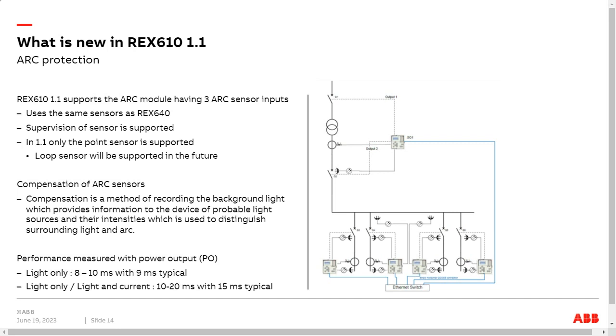Then there's something new here also, something called compensation of ARC sensors. This is something that you should do in the beginning. What it means is that you open up all the doors to the switchgear, switch on all the lights, and then it will record the background light. Why we do this is that it provides reliable information on, for example, how much light the device can expect in the background. And this is used as one criterion for the ARC protection function.